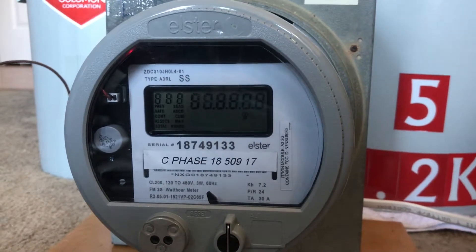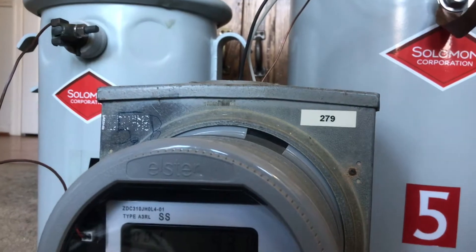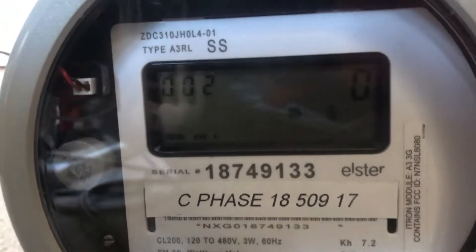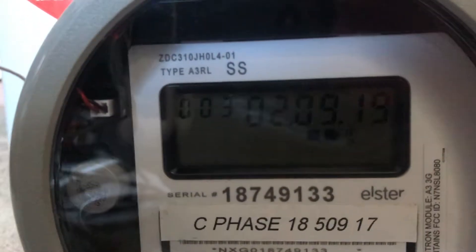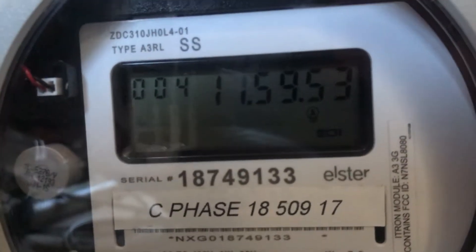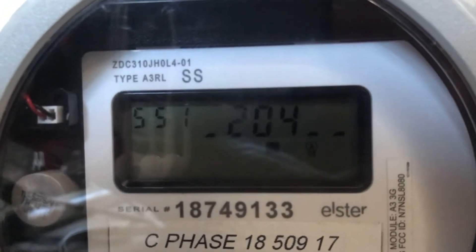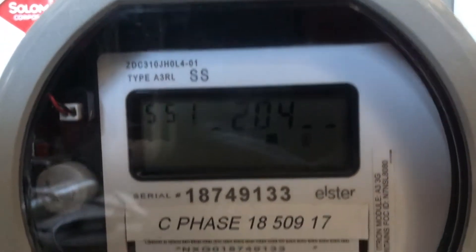I have it powered off of 240 volts, 120 to 240 transformer configuration using the 13.2. So this here can measure KVAR, KVA, and kilowatt hours. These are usually more used in commercial type settings, even though my power company does occasionally use these on class 320 services.